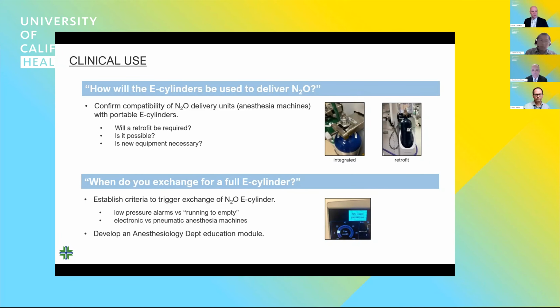The exchange trigger, when do you exchange for a new e-cylinder? That's something that you and your team in collaboration with your clinicians need to figure out. That could either be when your anesthesia machine fires a low pressure alarm from the cylinder, or it could be running the cylinders completely to empty. Those are some of the options. You'll have to, again, through your assessment of your infrastructure, understand if your machine has an alarm. Is that an appropriate trigger for you? Are you comfortable with that? Make sure your clinicians are educated as well.